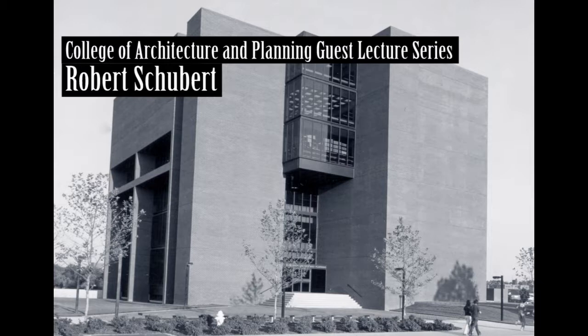The next one is a David Wright residence, also located in Santa Fe. It's semi-cylindrical in shape, an adobe type of construction. The wall size changes from 17 inches at the bottom level to 13 inches at the top floor. The walls are covered with polyurethane insulation and covered with stucco. Storage in the building is provided by water-filled drums along the front wall at the bottom and also the floor. The floor is a brick floor with sand that gives about a 24-inch thermal capacity.